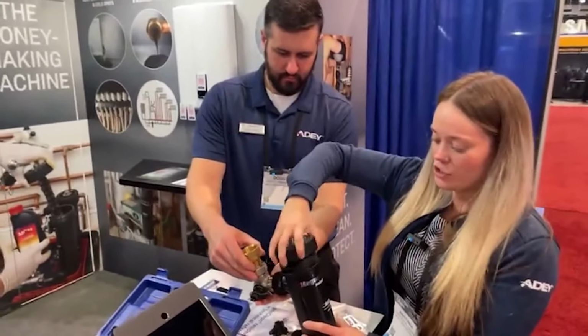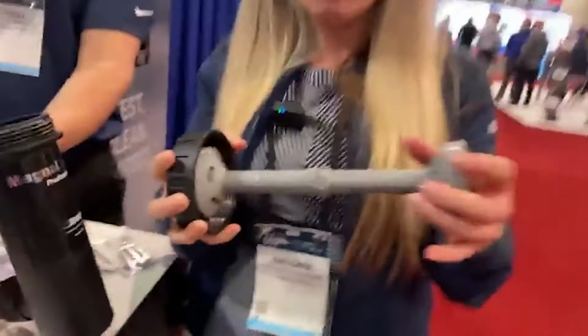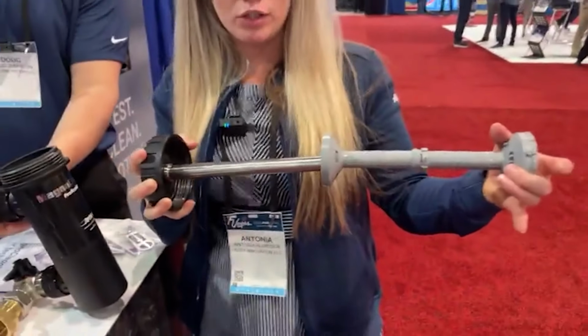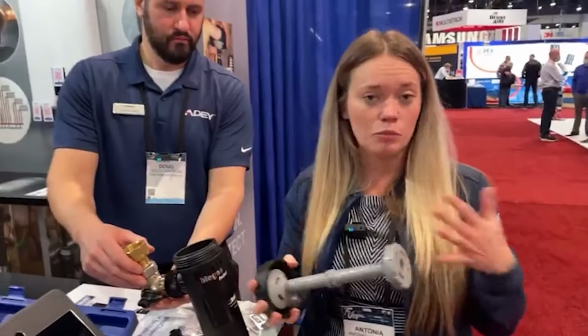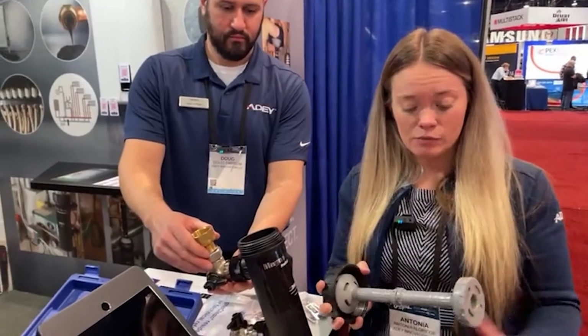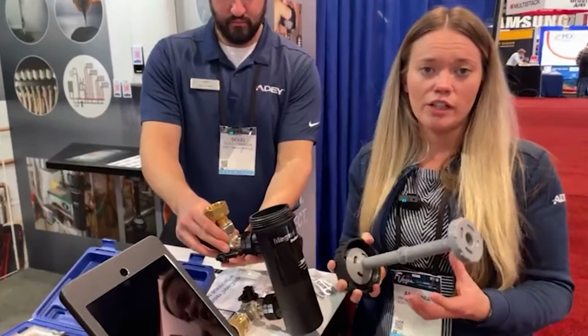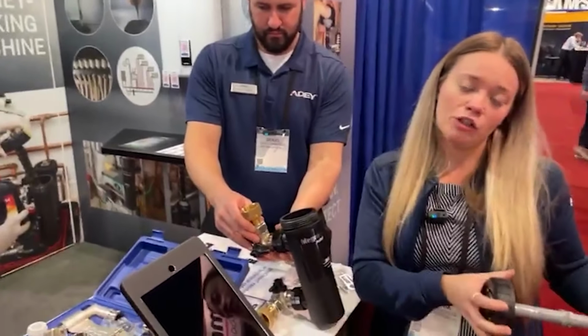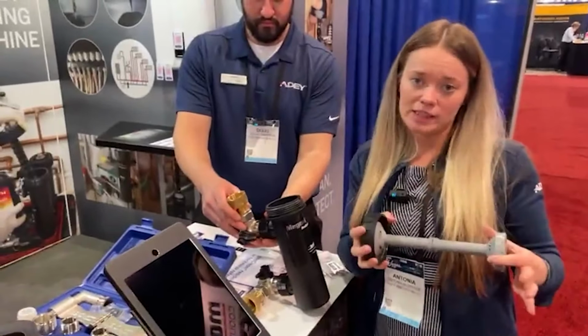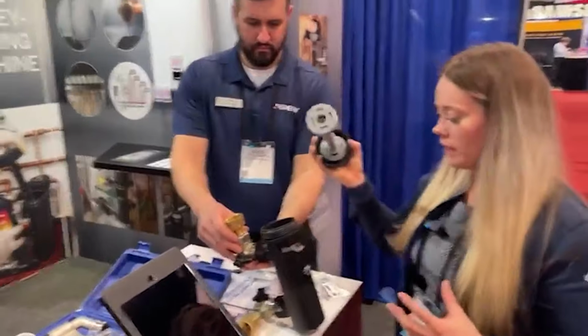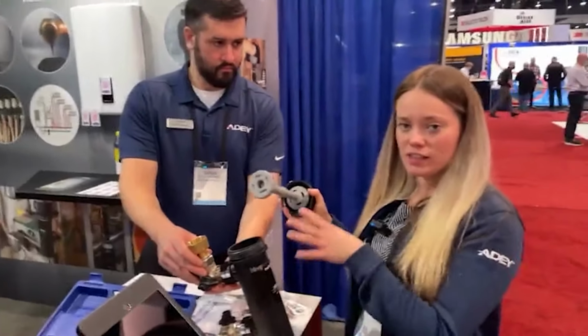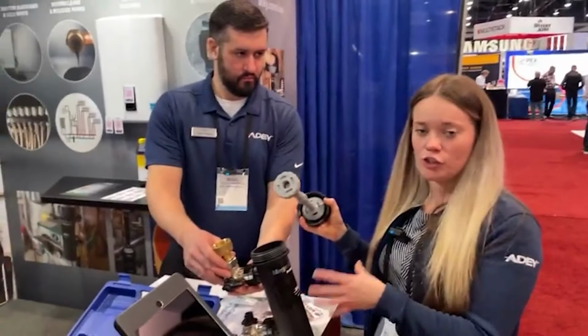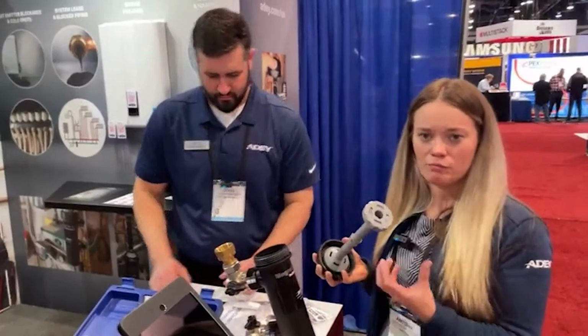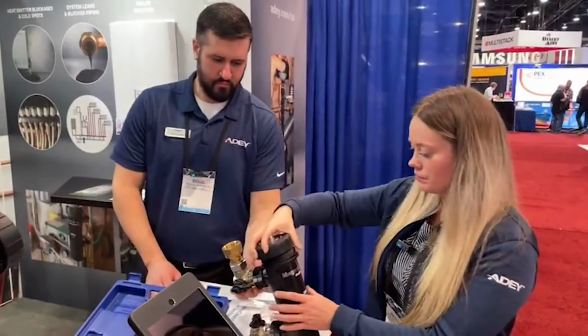Inside here is the actual magnet, so the magnet is underneath the sleeve. The reason for this is simply for easier servicing. The magnetite captures on here, and when you take that out, you just take it over to a sink and rinse it off, and you're good to go again. The beauty with this is that you can see inside all of the canisters, so you know when it's completely clear of magnetite and scale.